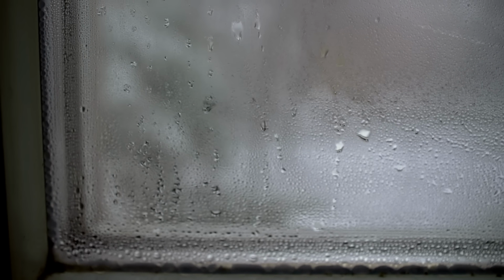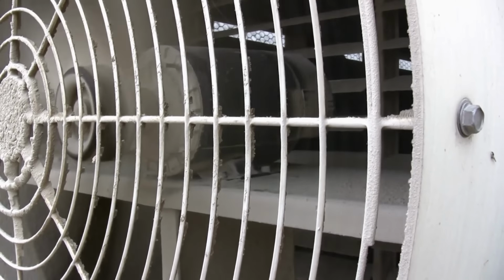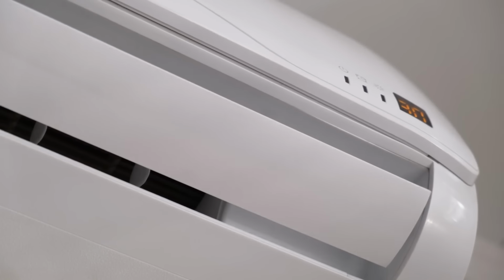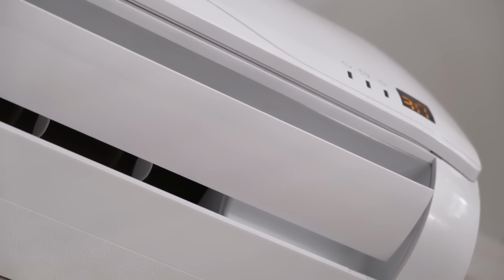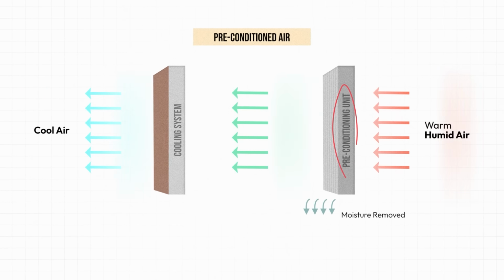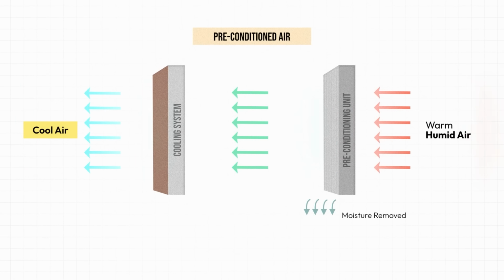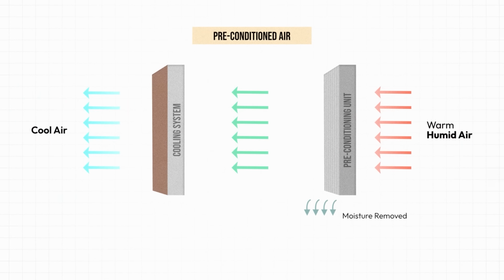This is because humidity in the air ramps up the AC's workload by increasing the energy required for temperature changes. This is because it requires the water vapor to change phase into a liquid, which is an energy-intensive task. Therefore, preconditioning air before it's cooled can offer huge benefits for air conditioning.